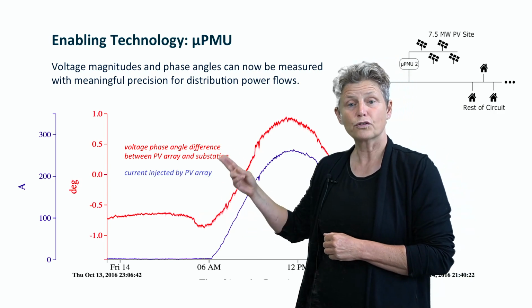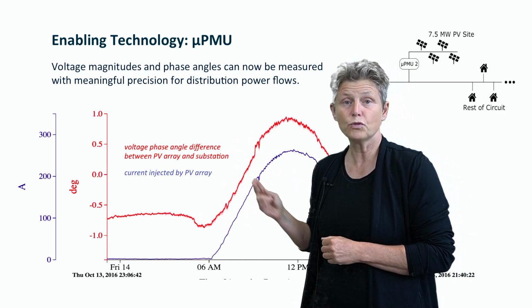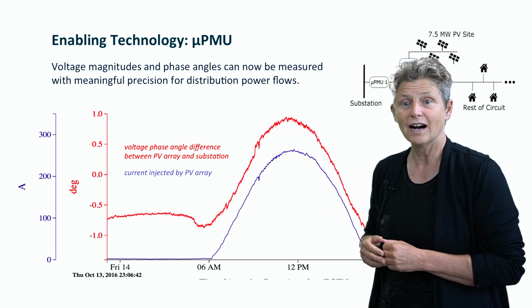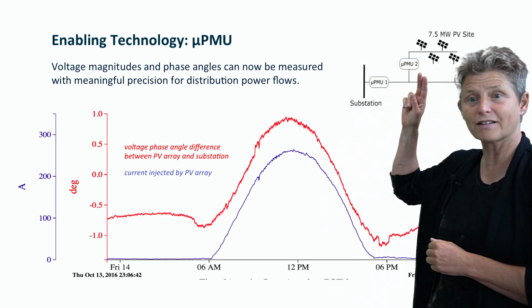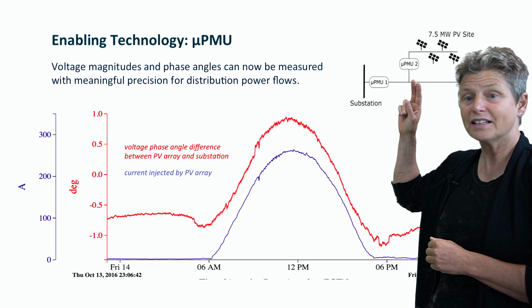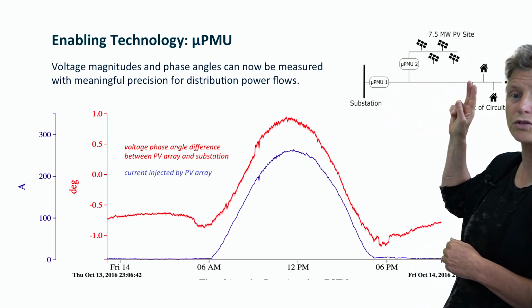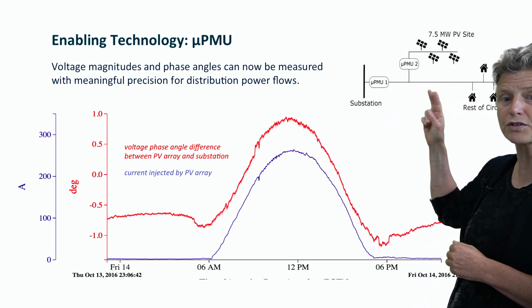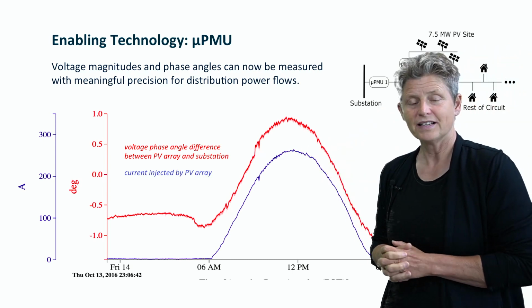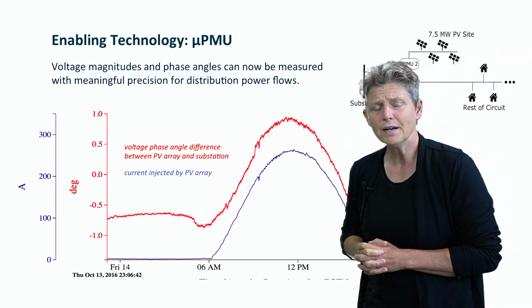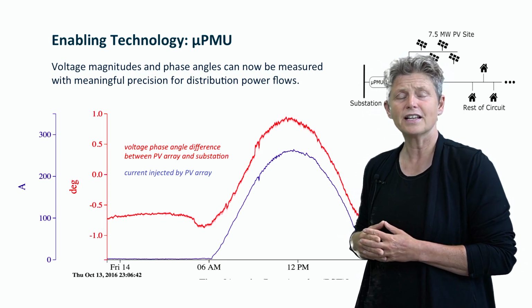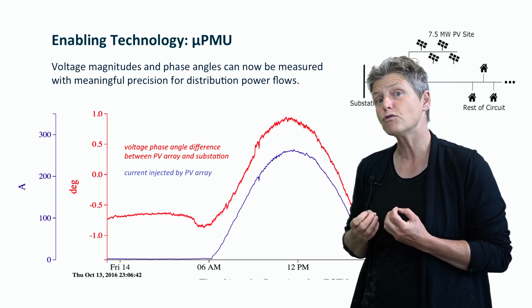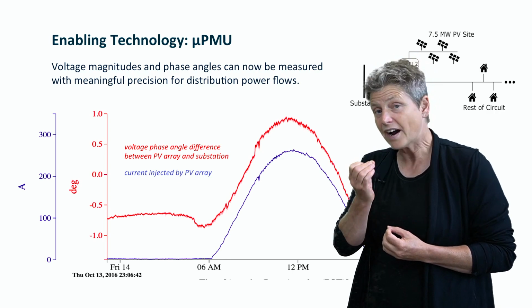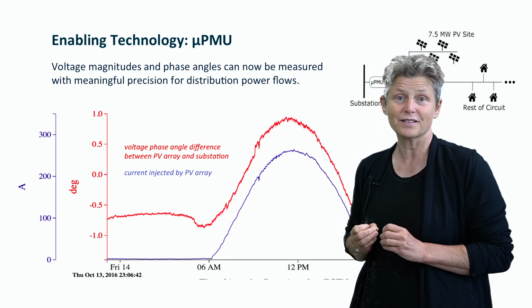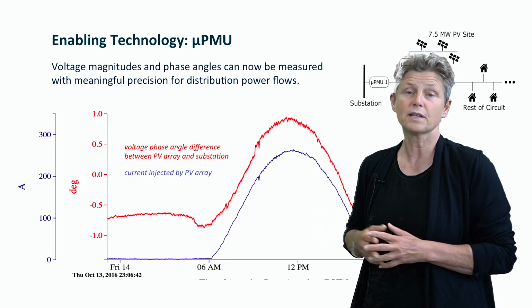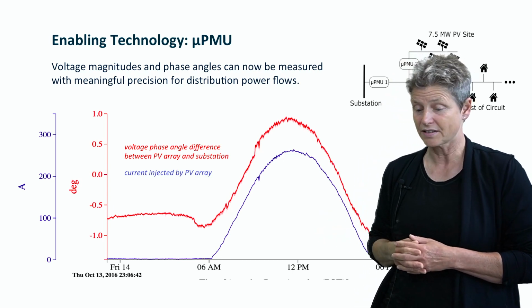But that voltage phase angle difference between the two PMUs corresponds fairly closely to the power injected here by the PV site. It doesn't correspond exactly because there's also load here from the rest of the circuit that's not captured in this blue diagram. But the important takeaway here is the precision that's needed, and without really fine-grained, precise voltage phasor measurements, you couldn't imagine even doing phasor-based control at this scale.